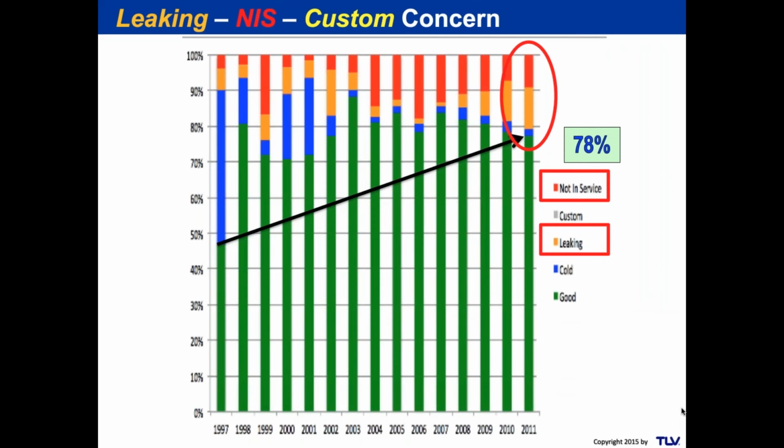Now this site we took a look at before, if you looked at part 1, and here from 1997 to 2011, we've got really great data, and look what they're doing. They got rid of these cold failures where they were having a lot of problems. They were knocking out turbines right and left on their 400-pound system. They got rid of these cold traps, and they moved this up to only 2 or 3% cold. That is awesome.